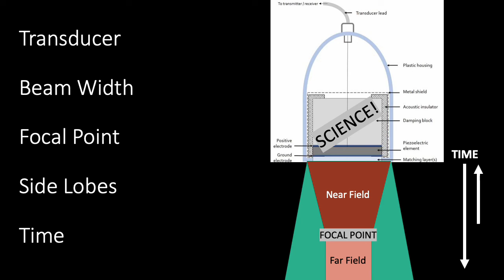So even though we think about the beam coming out of the probe as this small credit card beam that's very precise and in line, in fact it's really more like this. We can't control the sound waves like we can control a laser beam. We can't pinpoint exactly where we want to direct those waves. So yes, there is the main beam, but unfortunately the other side lobes, the beam width, these other concepts, they radiate outwards. And the machine does the best it can to avoid those other errant or abnormal frequencies or signals. But again, it's not a perfect machine. Sound will travel outward in kind of a circular pattern like we see with waves on a pond.